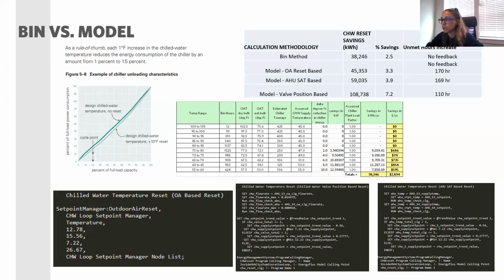The next one is based on the supply air temperature. Now we're using the sensor as the discharge temperature of the air handling unit, comparing it against the set point, flagging accordingly, and then modulating the chill water temperature based on that. We're seeing similar unmet hours. But the important thing is that, based on our flagging condition, for example, if it is not making the temperature more than 2 degrees, flag it. We could reduce it down to 1 degree, or we can say if one coil is requesting more flow, then start reducing the temperature. At least we know it is in our control.